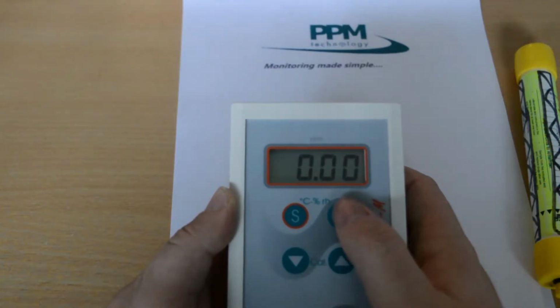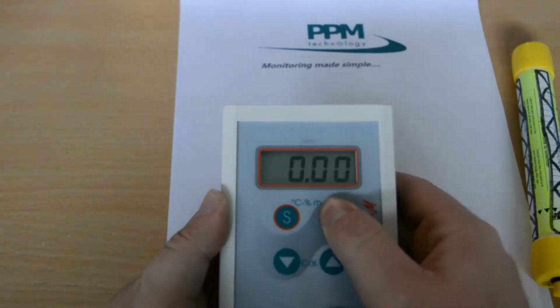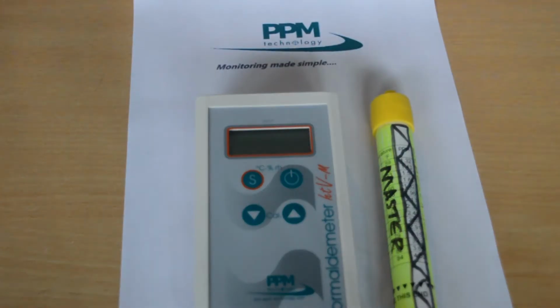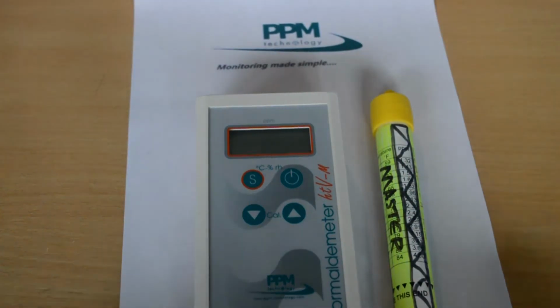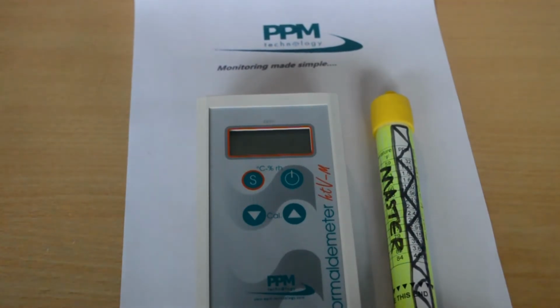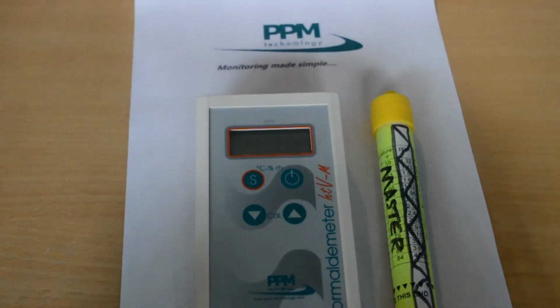Because the reset deletes the calibration information from the instrument, the display will flash the set and cal message each time it's turned on. This warning will be removed when the instrument is correctly calibrated, as in the calibration adjustment procedure video. If after a reset you are still experiencing problems, then contact PPM Technology or your distributor to arrange a service.